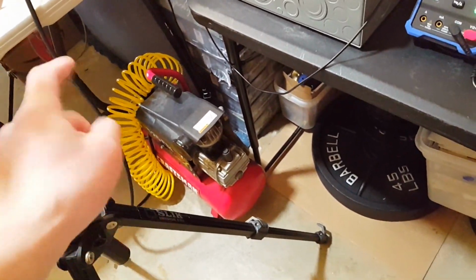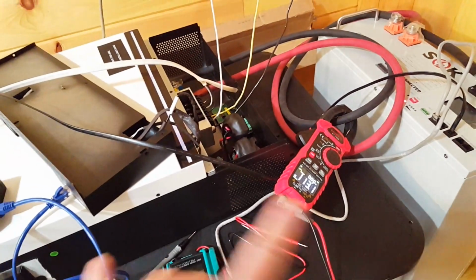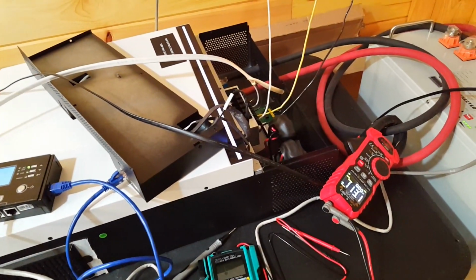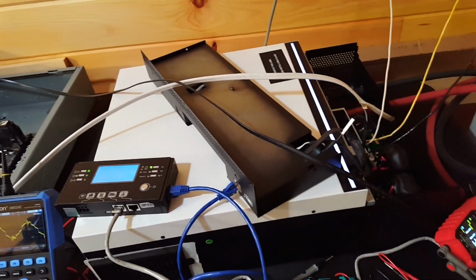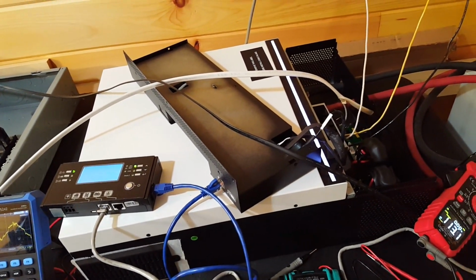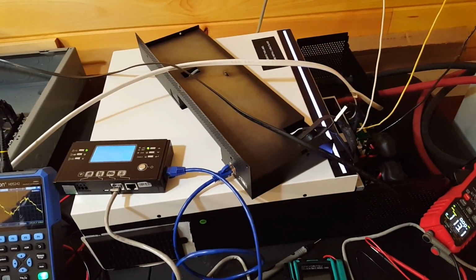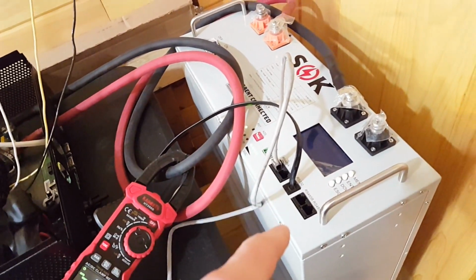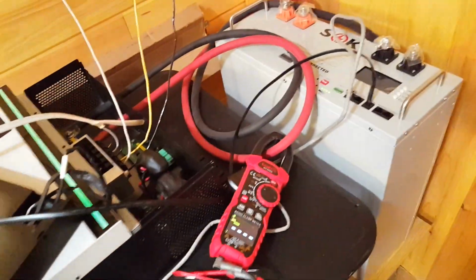The few times we have tried starting this air compressor with these two battery inverter combinations, it failed to do that twice already. I think we tried a total of about 4 or 5 times. It had 2 failures. It's not looking too good. This is supposed to be able to do 100 continuous and 125 surge. We'll give it another try. It sometimes works, sometimes doesn't.